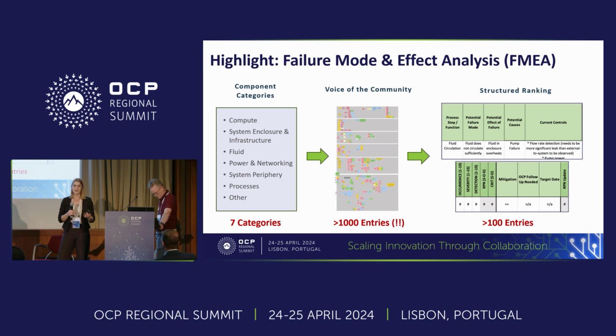The output of this will be specific guidance that the OCP community can provide to IEC, specifically for 62368, to have a new entry in that existing standard that's relevant for immersion cooling. This is important because whenever you are a facility owner-operator looking to adopt immersion cooling, you may have to talk to an authority having jurisdiction, some building code expert, or some standards expert.